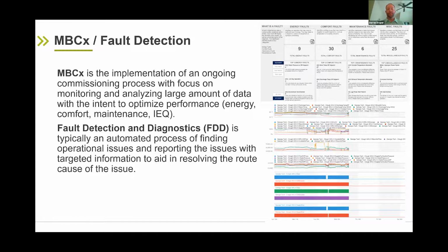That basically means monitoring-based commissioning doesn't necessarily require an automation process. It could simply be a commissioning agent utilizing a building automation system front end, or physically being in the building and using a large amount of data to perform that activity on an ongoing basis.